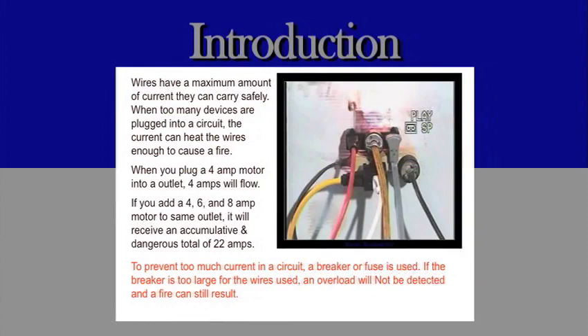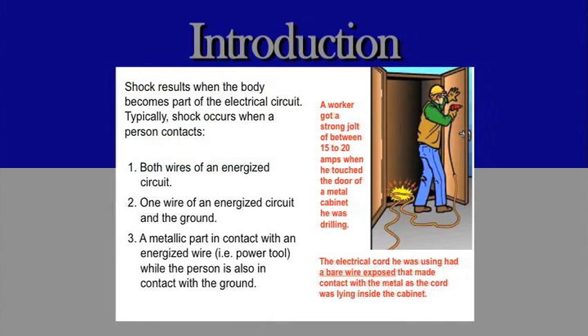Overload hazards. Wires have a maximum amount of current they can carry safely. When too many devices are plugged into a circuit, the current can heat the wires enough to cause a fire. When you plug a 4-amp motor into an outlet, 4 amps will flow. If you add 4, 6, and 8-amp motors at the same outlet, it will receive an accumulative and dangerous total of 22 amps. To prevent too much current in a circuit, a breaker or fuse is used. If the breaker is too large for the wires used, an overload will not be detected and a fire can still result.